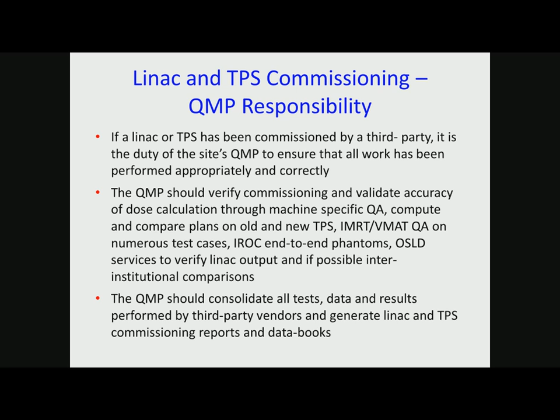And you need to have machine data books that are on the machine. You need to have an end-to-end test. A lot of sites don't do end-to-end tests, and I'm going to talk a little bit about the end-to-end test shortly. So MPPG, which came out in 2015, is a very good document. It guides you through the commissioning process.